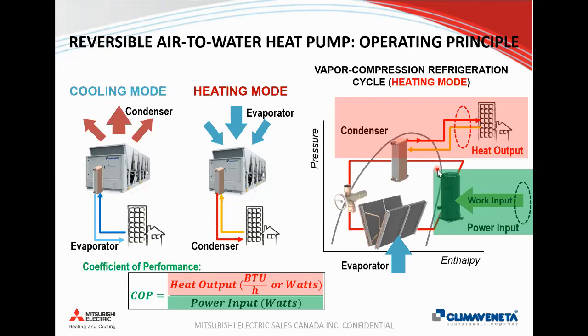And if we're comparing that to an electric boiler that always has a COP of 1, that makes a lot of sense because those are both electrical sources. So compared to an electric boiler, reversible heat pumps make a lot of sense because they're less costly to operate by a factor that's equal to the COP, and also will produce less carbon, even though we do have clean electricity in Ontario.